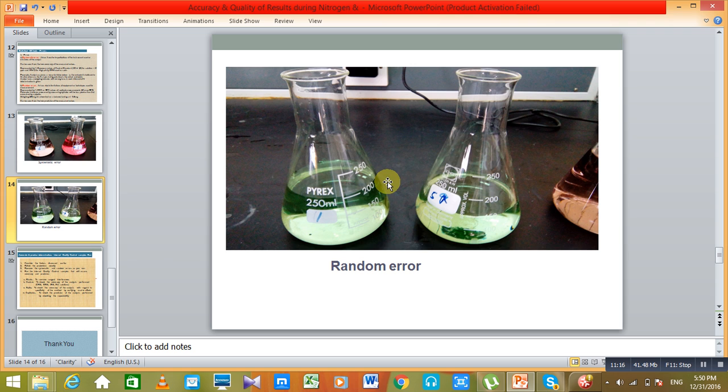So if you have not run the blank or the empty flask and you have run the first sample directly, you will have less distillate, less concentration, and less recovery. So this is actually a limitation of this machine in the very first sample.